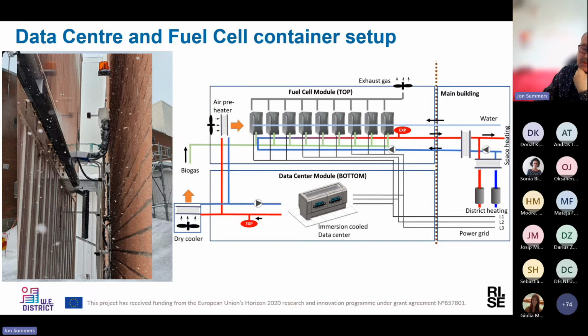The fuel cells would then ingest this warmer air, and on the back of the fuel cells, just before they exhaust, because they do exhaust some carbon dioxide and some water vapor, we needed to collect and harvest the heat from the exhaust. That's used to connect, not directly to the district heating, but to the building loop, which is the secondary loop.